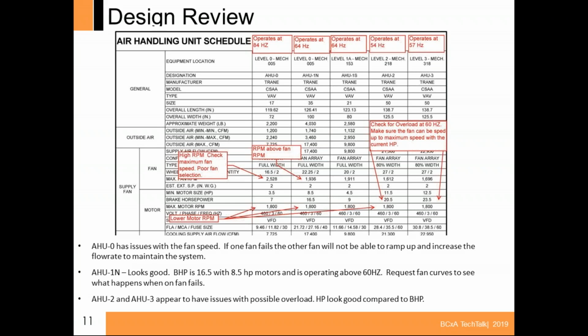And these are just 2 fan arrays. I've worked on up to 9 fan arrays. I've seen 12s. I have never worked on an ECM array. I get to do one of those next month. I'm really looking forward to that. But this is all, again, just for AC motors, and we're talking load side VFD voltages and amperage that the motor actually sees.